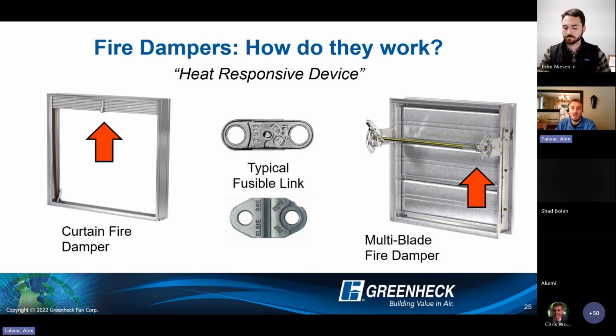But these fusible links do have melting temperatures. I probably got a slide on that coming up in a bit. But essentially, it's a heat response device. So once the heat increases, minimum 165 degrees, that link will separate and allow the damper to slam shut in the opening and provide the intended purpose, right? Prevent the spread of flame from one area to the other through the duct or opening in the wall.